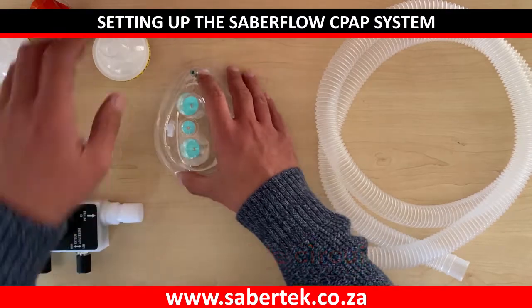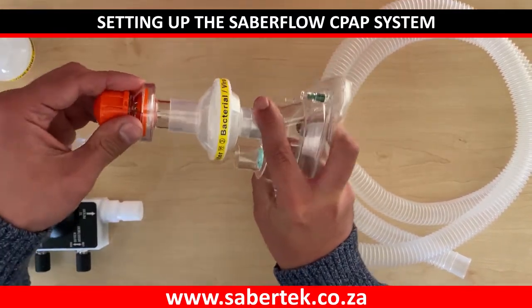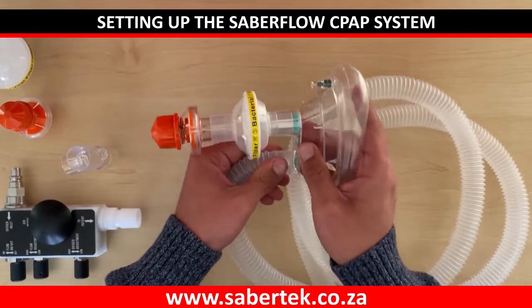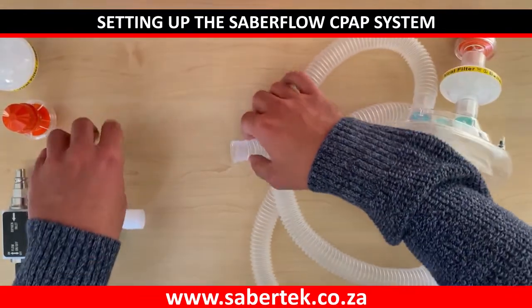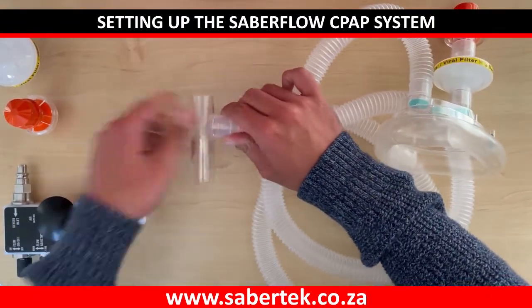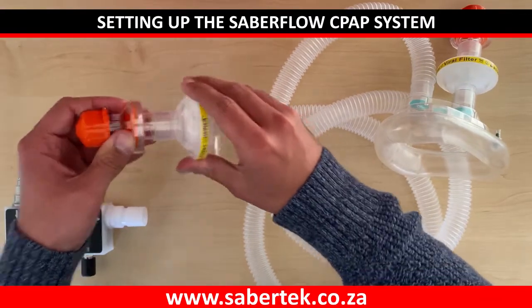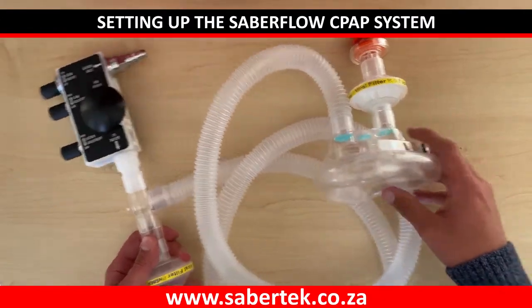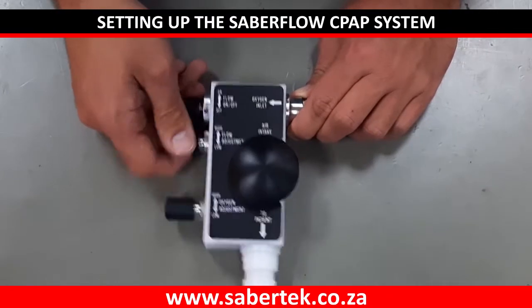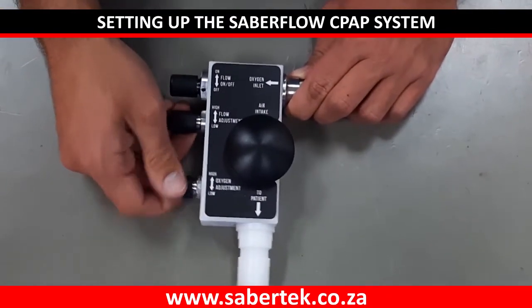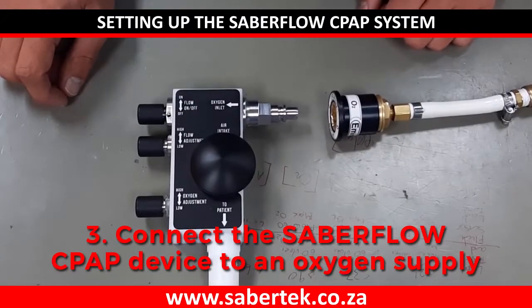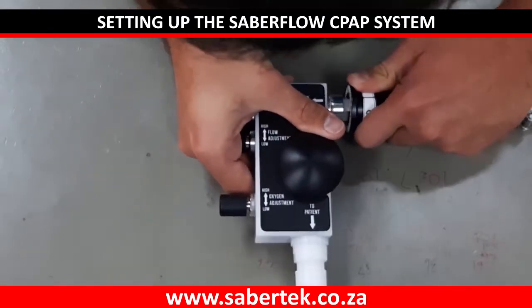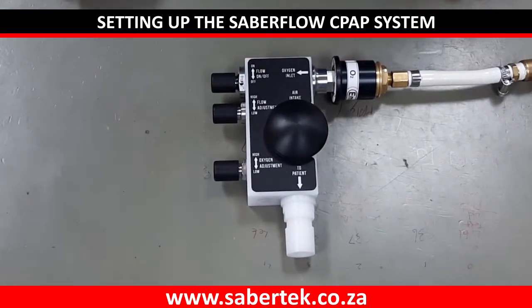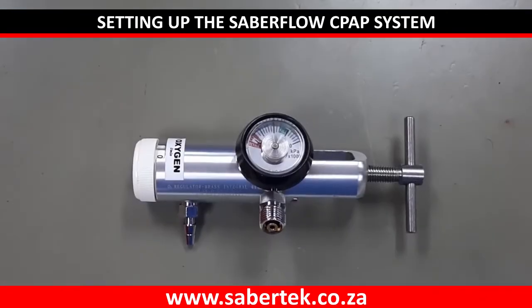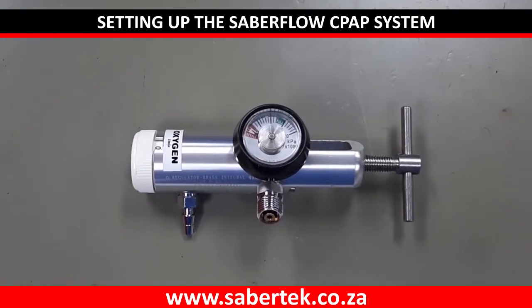1. Assemble the patient circuit as per the above diagram. 2. Turn all control valves on the SaberFlow CPAP device A, B, C off by turning fully clockwise. 3. Connect the SaberFlow CPAP device to an oxygen supply, either from a wall outlet or oxygen bottle. When using an oxygen bottle, a line pressure of 400 to 500 kPa is recommended. This is achieved with a pressure regulator.